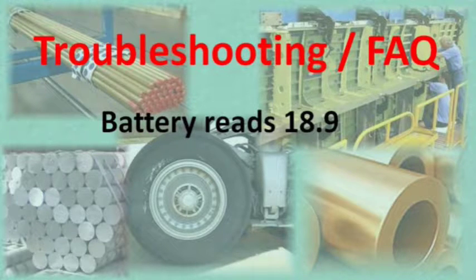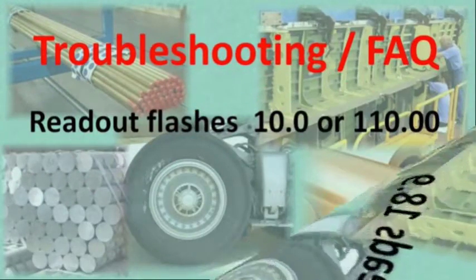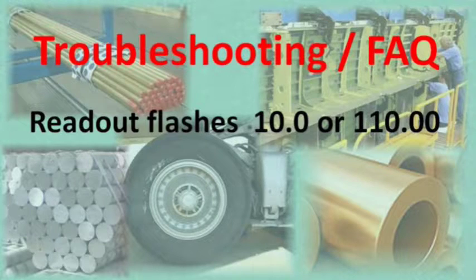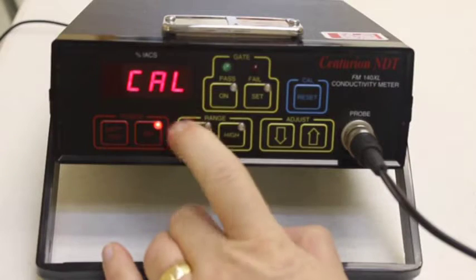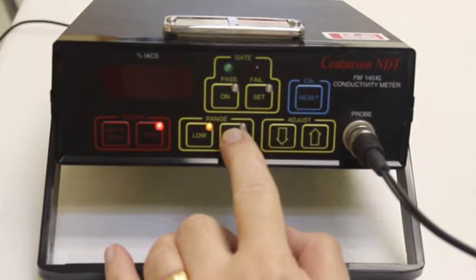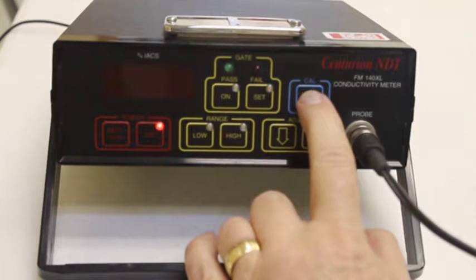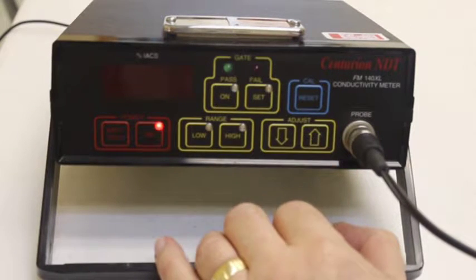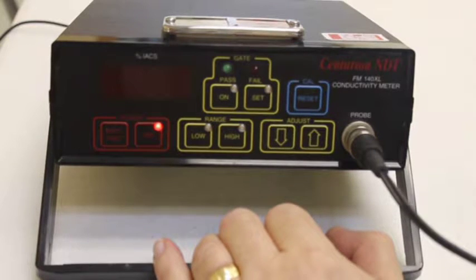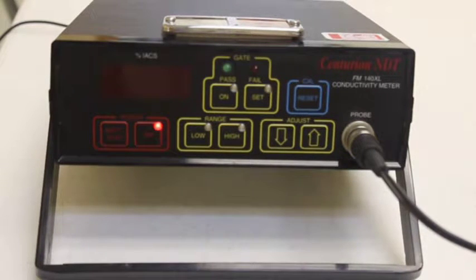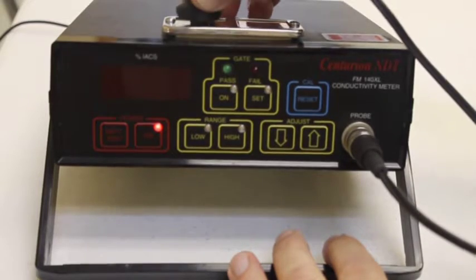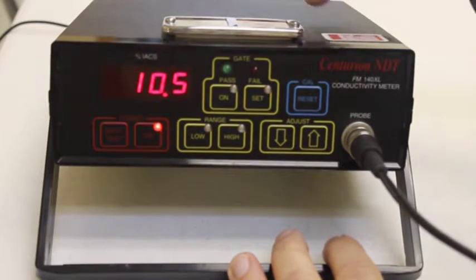This happens most often when the instrument is plugged in for an extended period of time and not allowed to occasionally discharge. There may be instances when attempting the initial setup that the display is either blinking 10 on the low end or 110 on the high end, and it seems like the arrows have no effect. The easiest way to get the instrument back into range is to do the following. Press the push buttons in this order: low, high, high, reset. 4 bars will light up on the display. What this does is set the instrument back to a default condition so that the initial setup can be accomplished more easily. Then simply calibrate as usual.